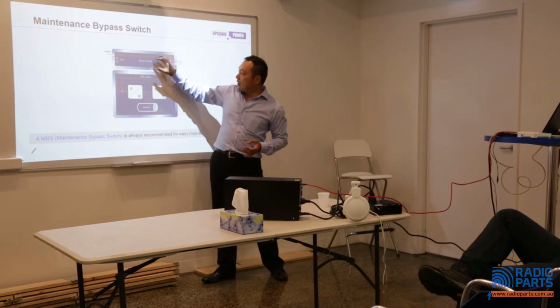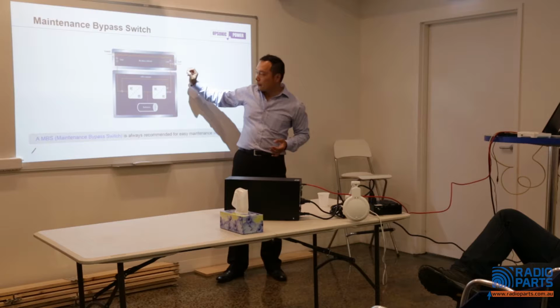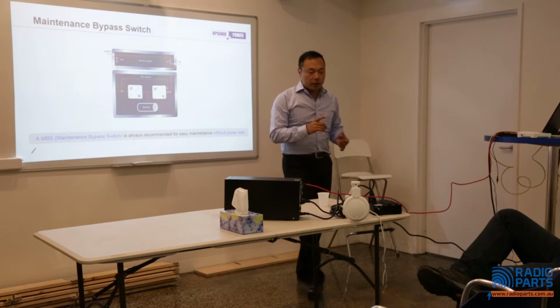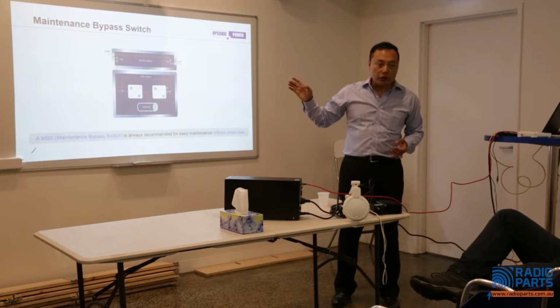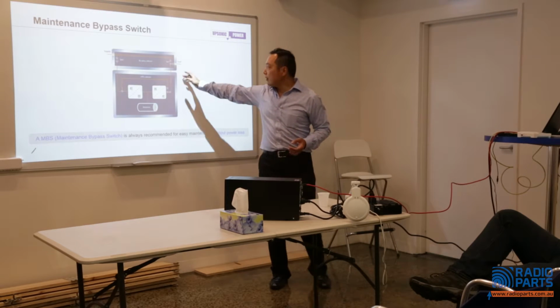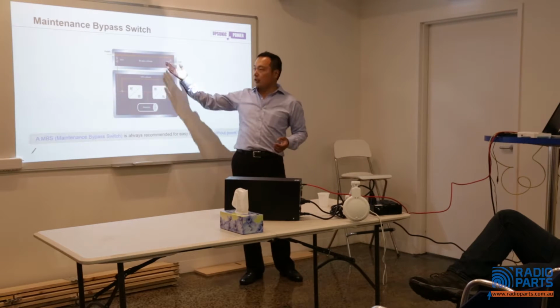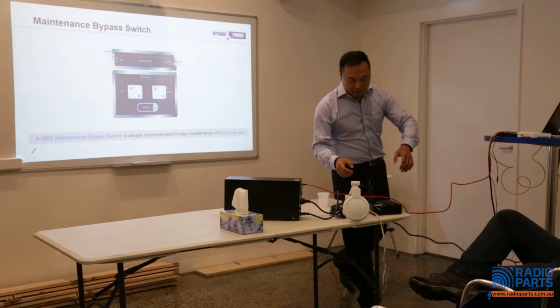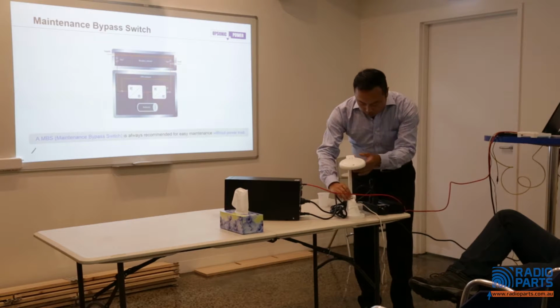Without a maintenance bypass switch, you have to disconnect it, and there will be power loss for the equipment. But when we install a maintenance bypass switch, you just turn the switch from normal mode to bypass mode, and then you just take out the UPS. It's still powered. Let's see how.